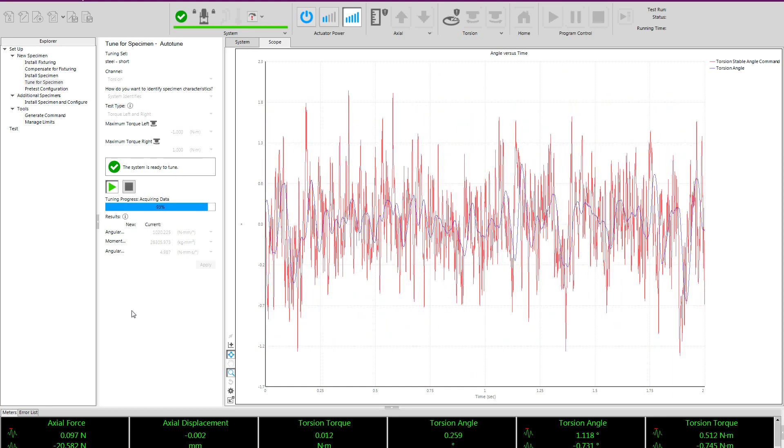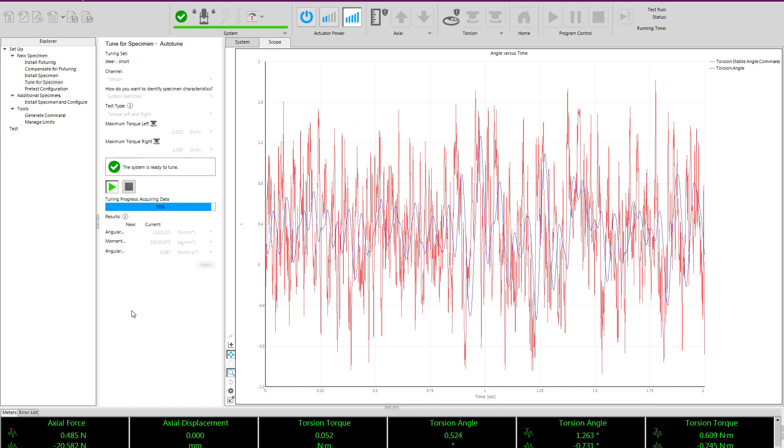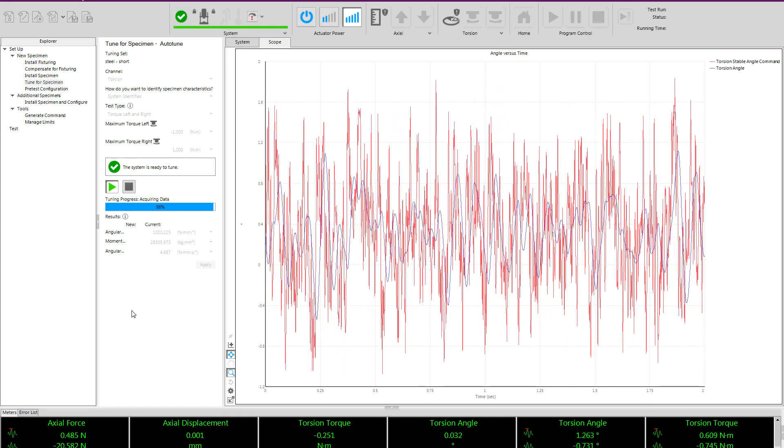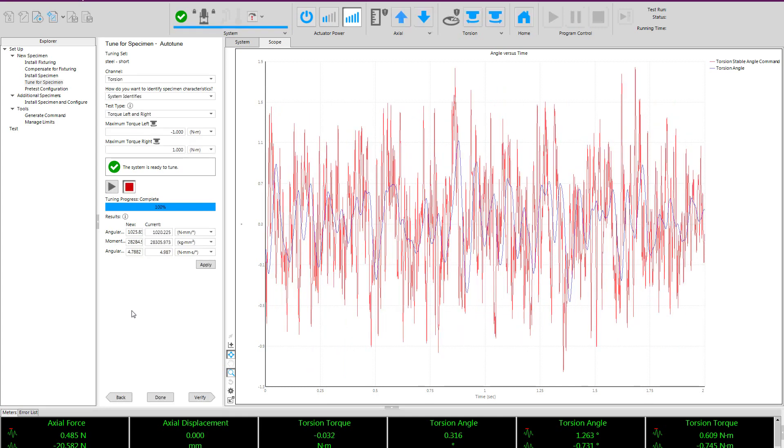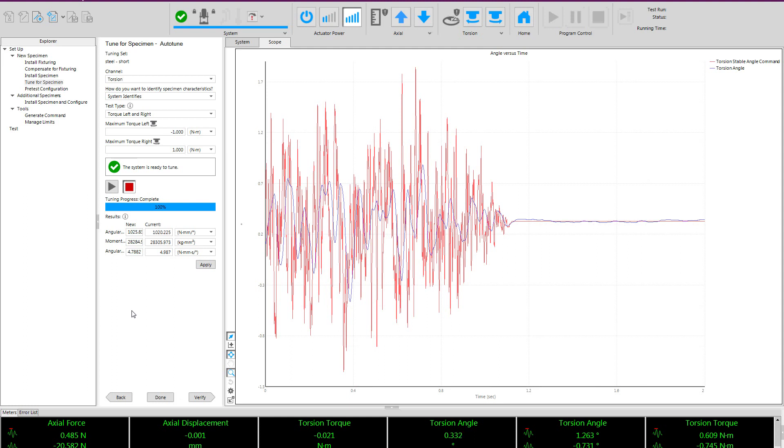As the procedure completes, you will see that the software reports the angular stiffness, moment of inertia, and damping of the specimen as it measured them. We then click apply, which creates the tuning values and enters them into the control system.